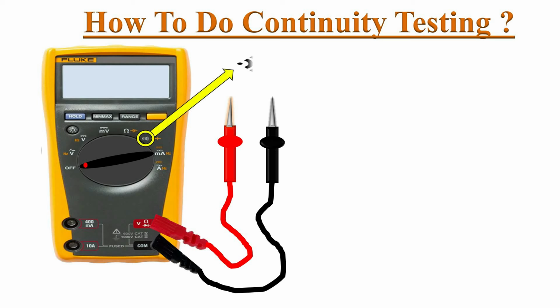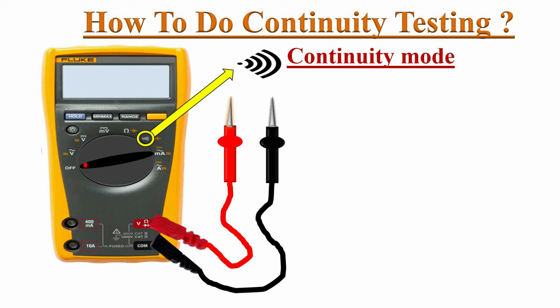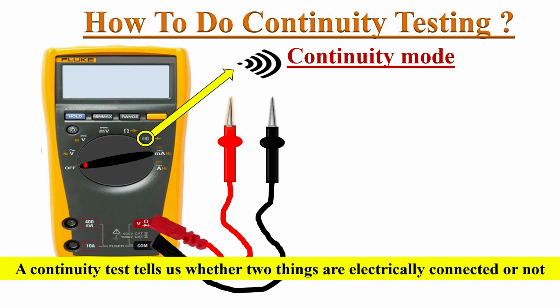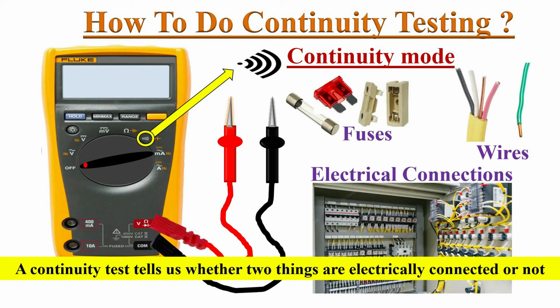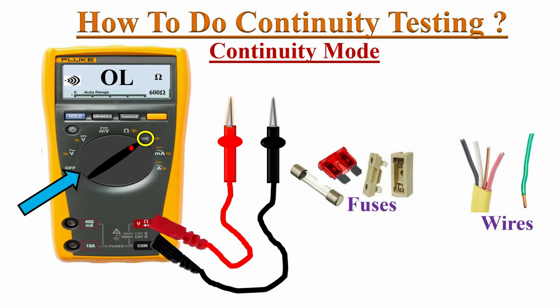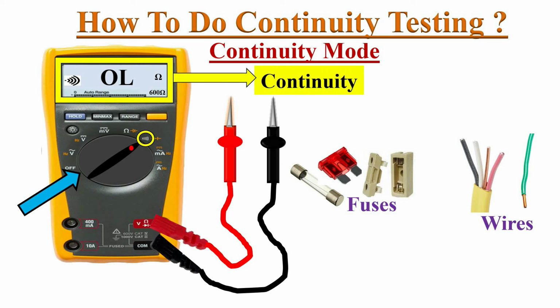Just identify this symbol on the dial. It represents continuity mode. A continuity test tells us whether two things are electrically connected or not. Continuity test mode can be used to test switches, fuses, electrical connections, and so on. For example, a good fuse must have continuity. Just turn the knob to continuity mode position. The multimeter switches on in the lowest resistance range and the continuity symbol appears on the screen.